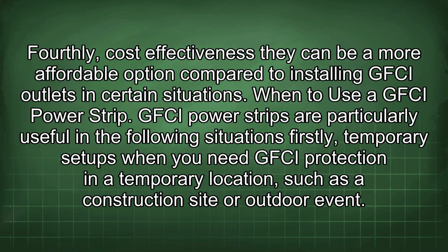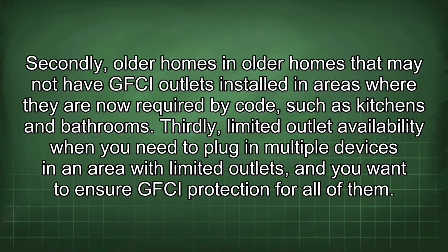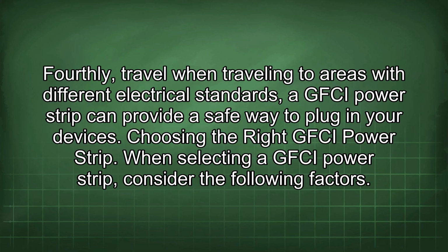When to use a GFCI power strip. GFCI power strips are particularly useful in the following situations. Firstly, temporary setups when you need GFCI protection in a temporary location such as a construction site or outdoor event. Secondly, older homes that may not have GFCI outlets installed in areas where they are now required by code, such as kitchens and bathrooms. Thirdly, limited outlet availability when you need to plug in multiple devices in an area with limited outlets, and you want to ensure GFCI protection for all of them. Fourthly, travel. When traveling to areas with different electrical standards, a GFCI power strip can provide a safe way to plug in your devices. Choosing the right GFCI power strip.